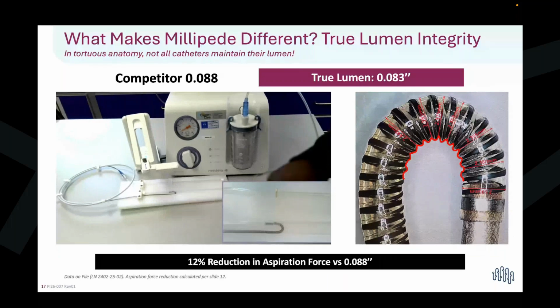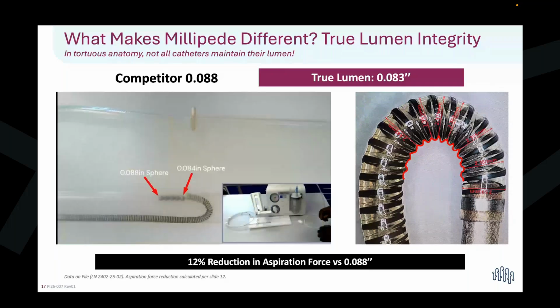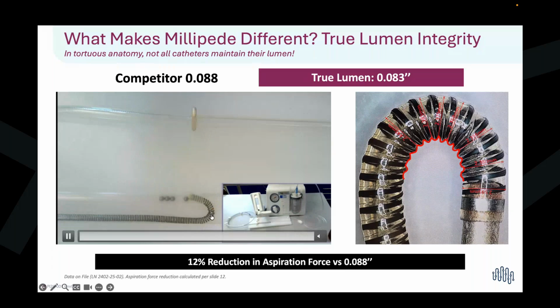So hold on, we'll load them on the typical commercially available 088 catheter that is not corrugated. And when we suck these through, only the 084 goes into the catheter and becomes lodged at that point of tortuosity. And so the unique corrugated design resists this ovalization around curves where the typical PTFE catheters with a coil design distally do not. And so this maintenance of the luminal diameter in areas of very high tortuosity is something that's very important to aspiration because you can imagine a thrombus would be stuck here in some cases where it would pass through a corrugated 088 catheter.